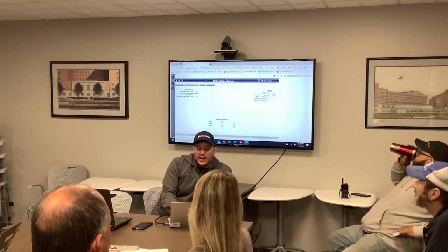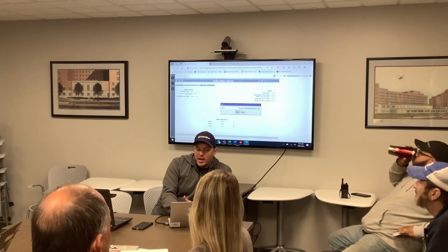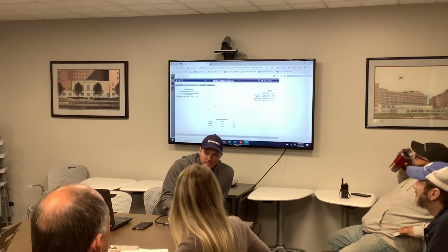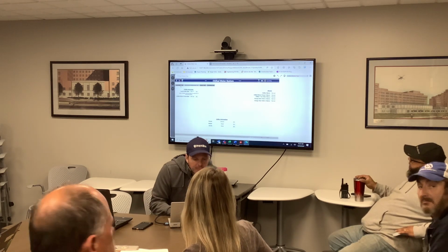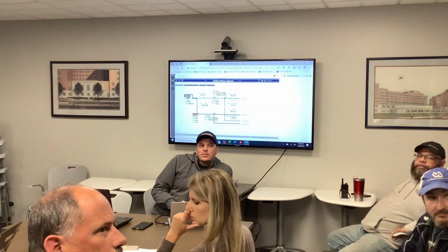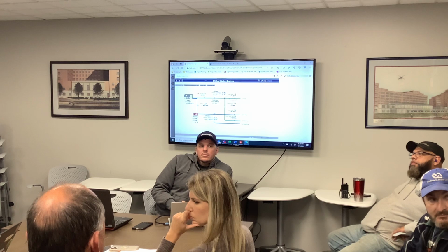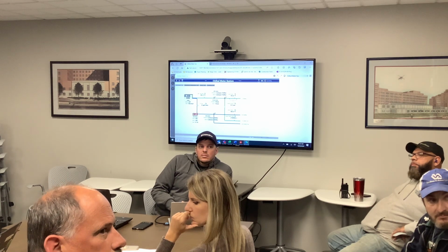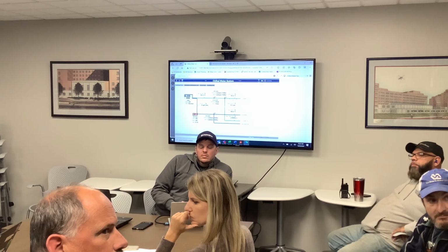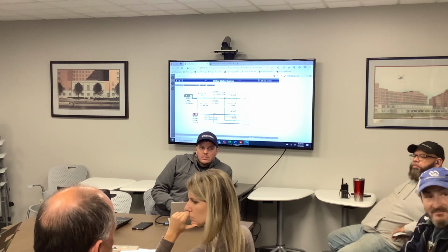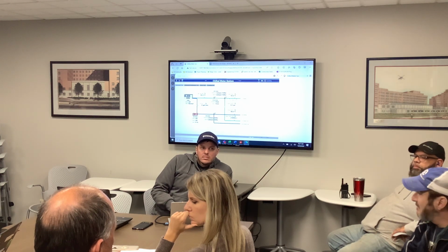So I have it set for 80 right now, we can go ahead and drop it down to 70 and it will turn over. I'll drop that to 65. And the chiller will turn over, right? But as far as ambient temperatures outside, we're in climate zone 5. Not last year, but the year before, over the past 5 years, we average a polar vortex. So there's a reason why we introduce inhibited propylene glycol to the system so we can operate at negative 35. Not saying it's gonna get that low, right.